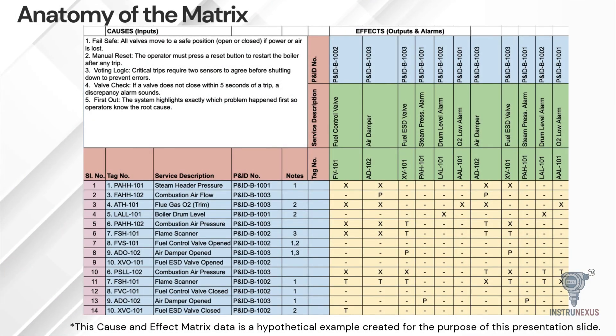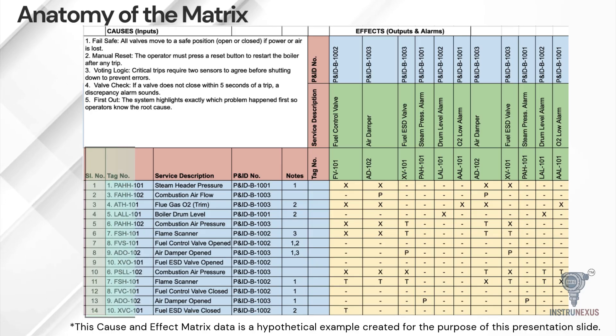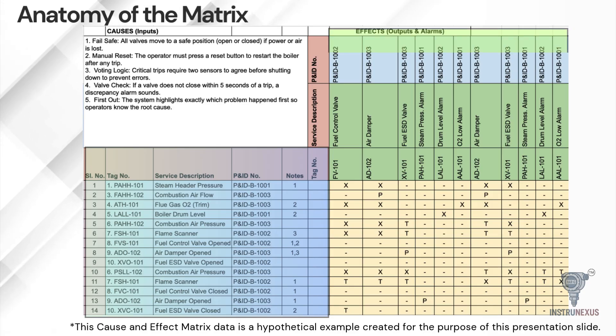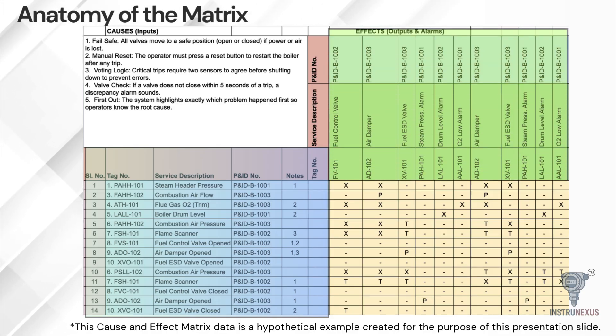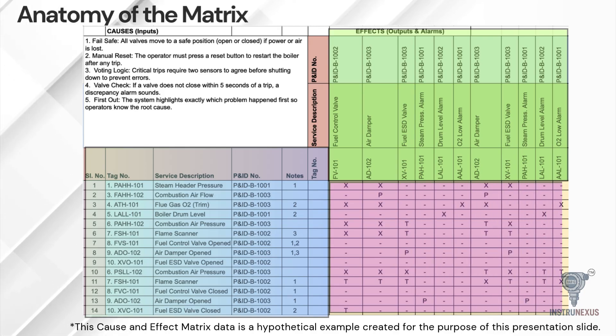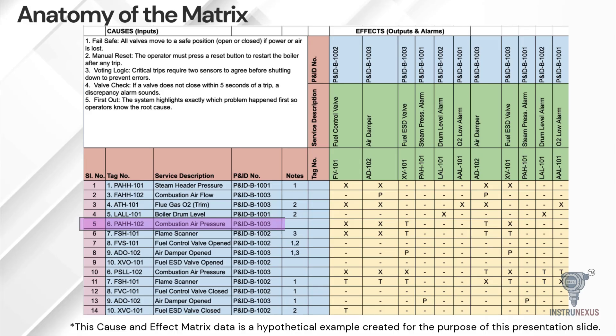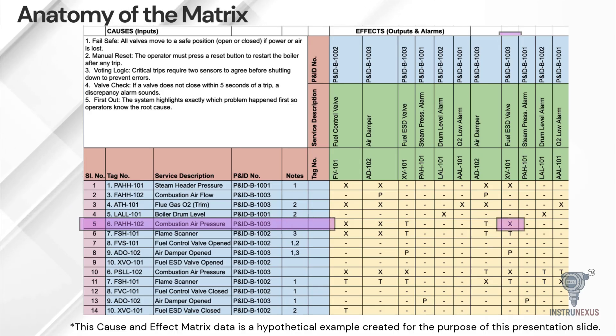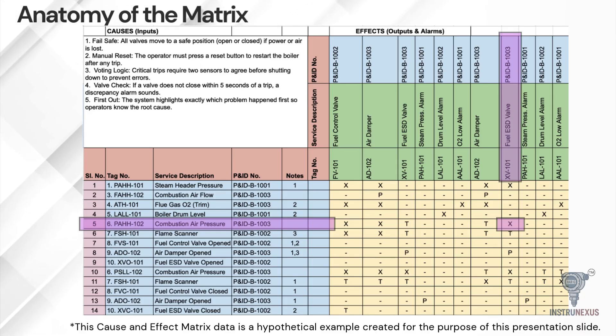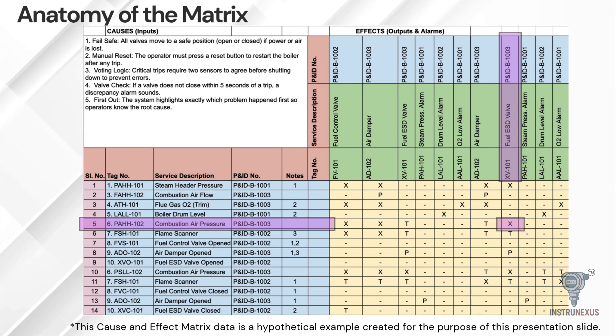Let's pause to look at the anatomy of the document itself. While formats vary, the logic remains the same. On the left-hand side, we list our causes — these are our sensors. Across the top, we list our effects — our valves, pumps and beacons. In the intersecting cells, we define the action. For example, if a specific pressure transmitter detects high pressure, the matrix might place an X or a trip command in the column for the inlet shutdown valve. We might also see commands to close specific valves or trip motors. This grid allows anyone to trace a horizontal line from a sensor and see exactly which devices will activate in an emergency.